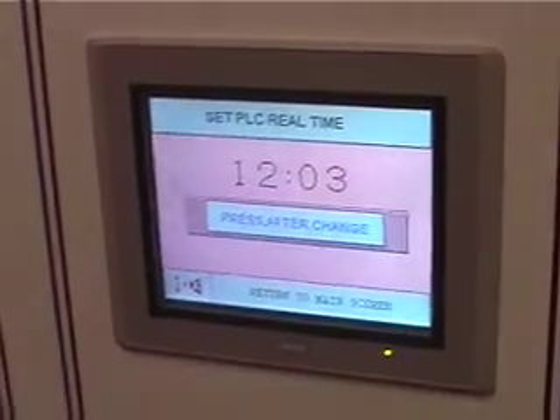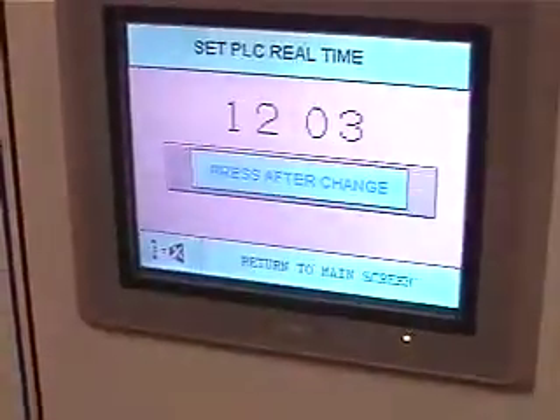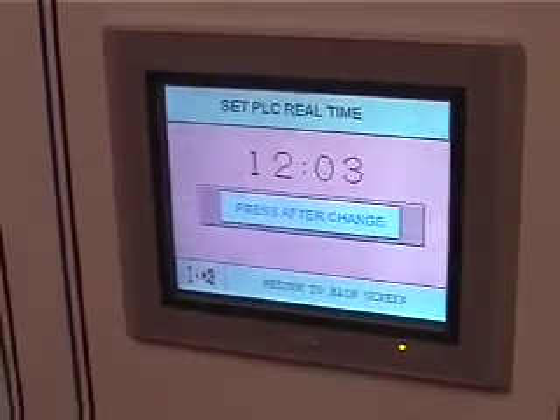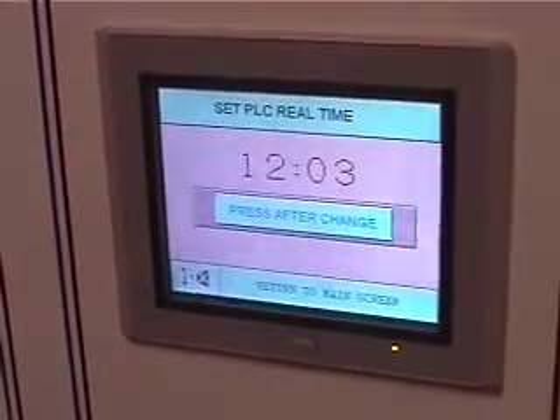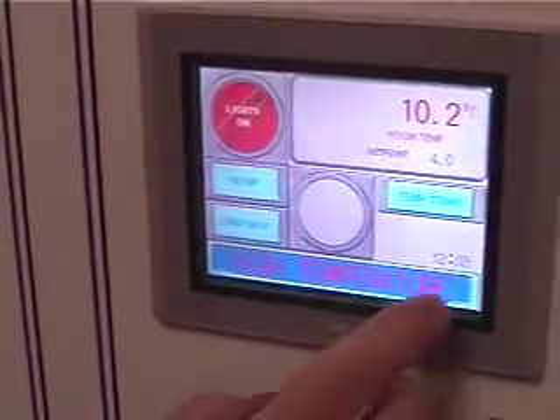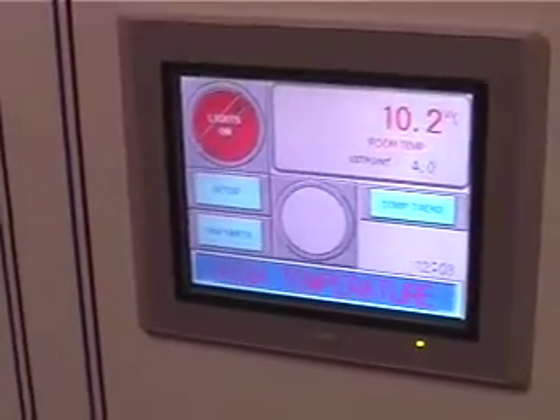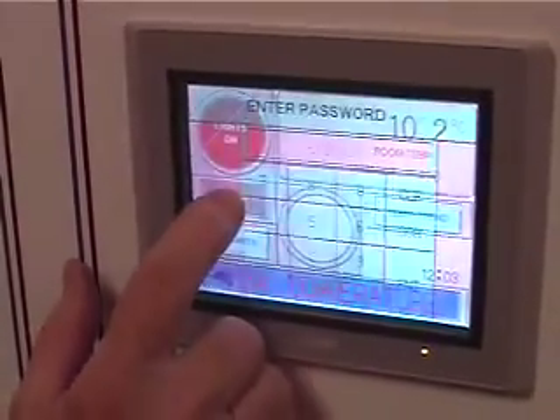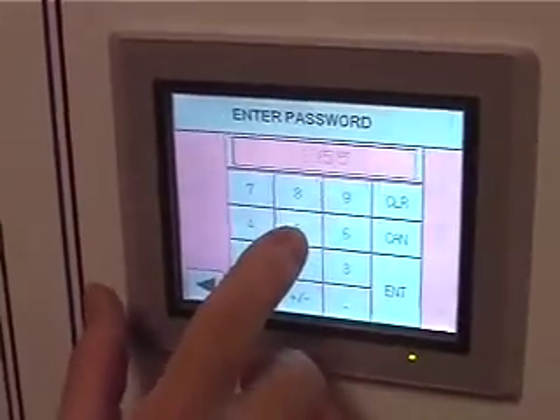There are special registers in the PLC that have to get that time to make it actual time. So we have this big button here that says press after change. What that does is it forces these numbers into those special registers. So we go back to the main screen, you see you've changed your time. Guys are saying, yeah, I'm going to come and do that all the time, Phil.